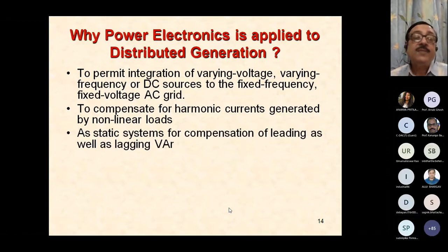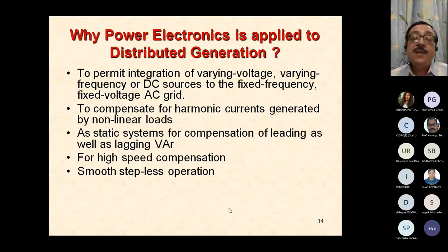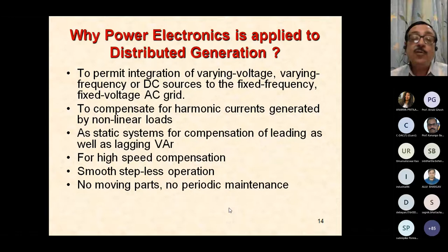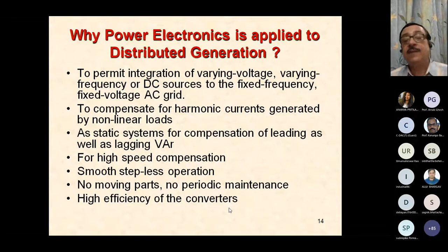The power electronics is used as static systems for compensation of leading as well as lagging VAR. It's used for high speed compensation, smooth stepless operation, no moving parts, no periodic maintenance, and high efficiency of the converter. Today, power electronic converters and inverters used for solar have efficiencies much higher than 95%. Some claim to have it close to 98%, but that is at specific loads.